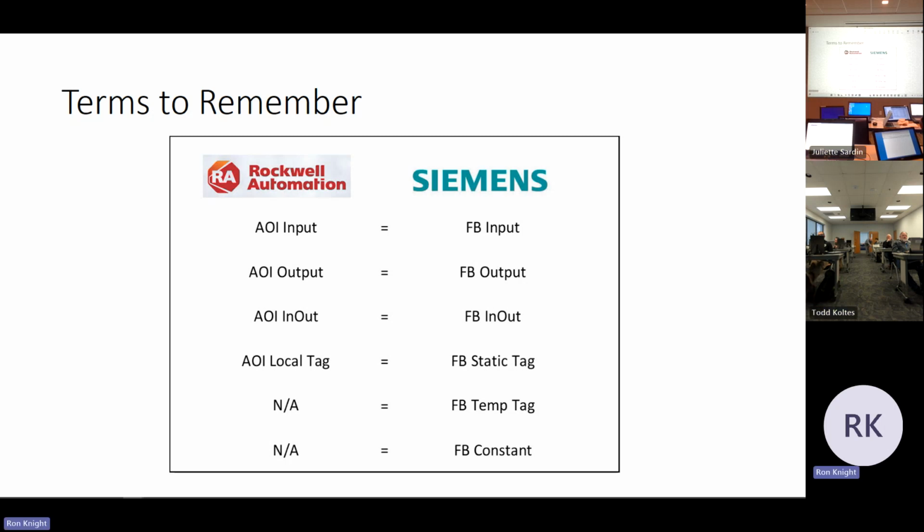And what do you have to use to flash the firmware? ControlFLASH. Yep, either ControlFLASH or ControlFLASH Plus. You need to download the firmware from the Rockwell website. Once you've got the firmware flashed, hopefully you don't brick the PLC. You don't lose power, or kick your Ethernet cable or anything crazy like that. I actually bricked my first PLC, and it was a MicroLogix 800, as a matter of fact. Right in the middle of flashing the firmware, it bombed, and I never could get communications reestablished. I had to send it back and get a new one.